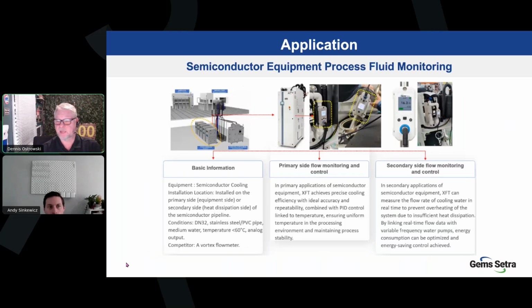I promised you some application examples. First one we have here is in the semicon industry. Semiconductor equipment, they have primary and secondary loops. When they're using chilled water, there'll be a primary loop. The primary loop is bringing facility water through a chiller, and then that is fed into what's called a secondary loop. That secondary loop then is going to your semiconductor equipment, right?